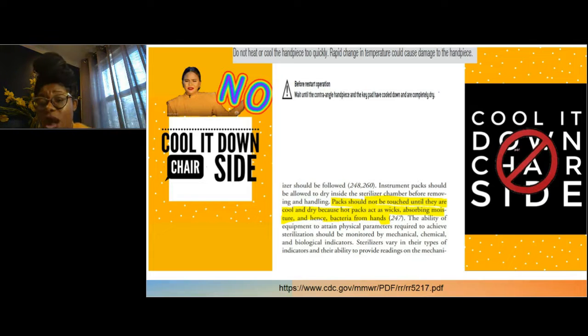Just by touching it hot, wicking happens. And you will see here in the middle is from the CDC guidance that says packs should not be touched until they are cool and dry, because hot packs act as a wick, absorbing moisture and hence bacteria from the hands. Not to mention placing it underneath water, which just allows for microorganisms to come in to then have a means to be on the handpiece. Chairside cooling should never occur.